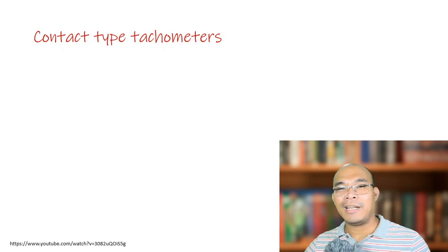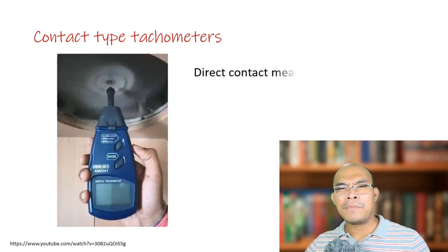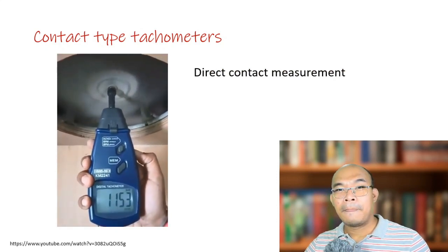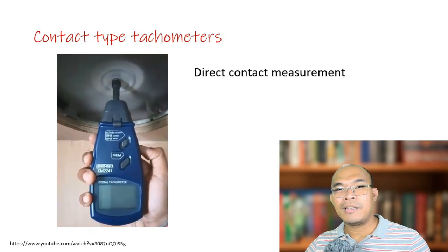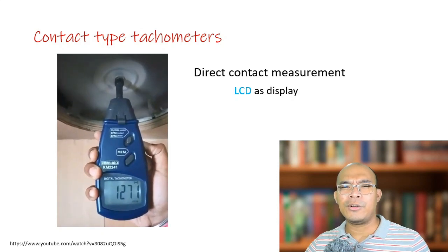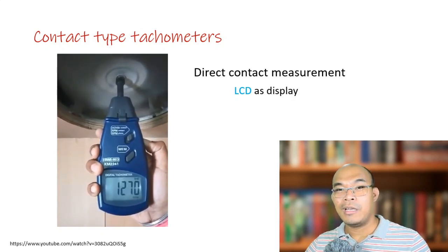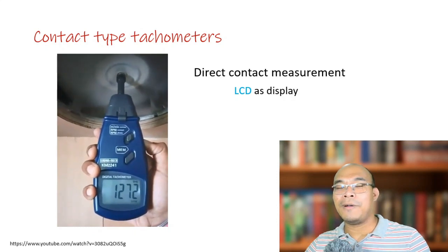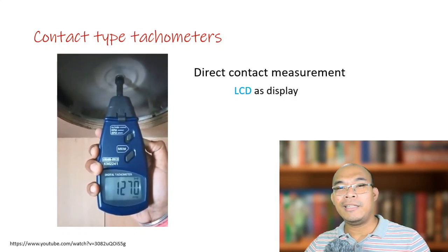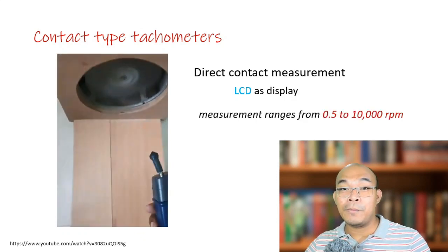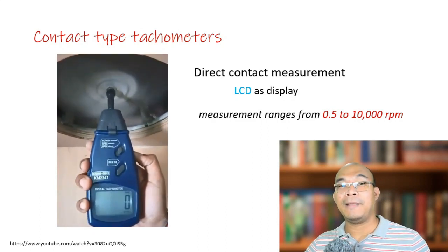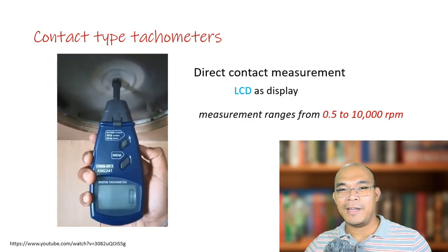The first type of digital tachometer is the contact type device, which requires direct contact with the object being measured. This device uses an LCD as a display. The operational temperature ranges from 0 to 40 degrees Celsius, storage temperature ranges from negative 20 to positive 55 degrees Celsius, and the rotating speed measurement ranges from 0.5 to 10,000 RPM — though this will always vary depending on the specification of the device.